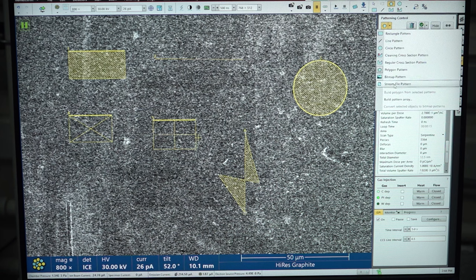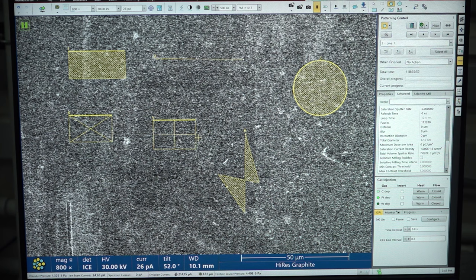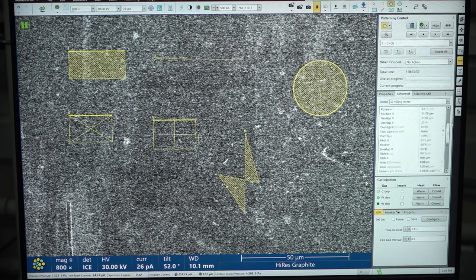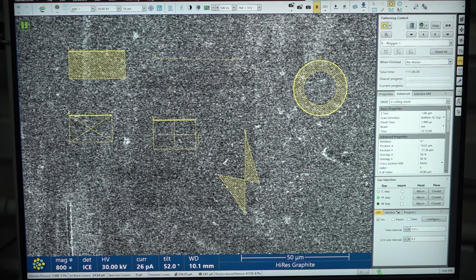You can load a bitmap file or stream file. The rectangle pattern is generally used for making contact pads using precursor depositions. A line pattern can be used for making a cut or deposition. Circular patterns can create a through hole, or you can make a pillar structure by defining your inner and outer diameter. The regular cross section is for rough milling of trenches. The cleaning cross section is for cleaning the wall of the cross section. The polygon can be of any shape. These are the patterns that can be defined manually for milling or deposition.